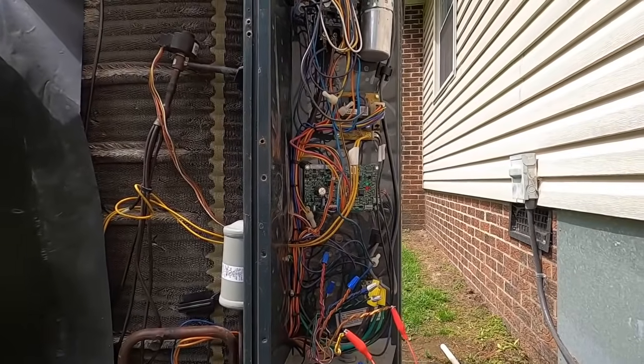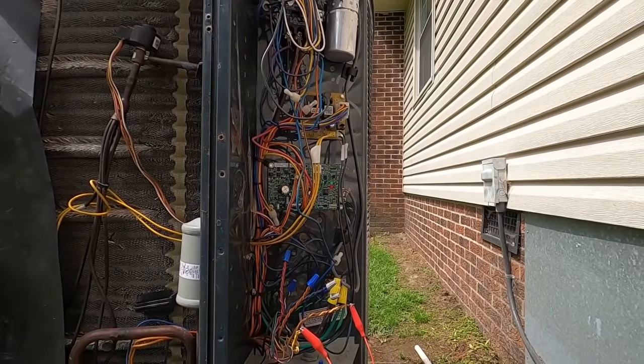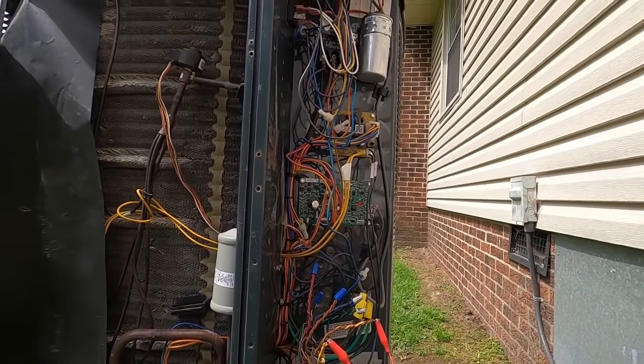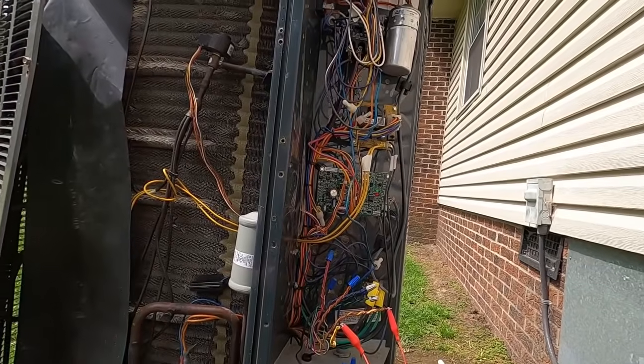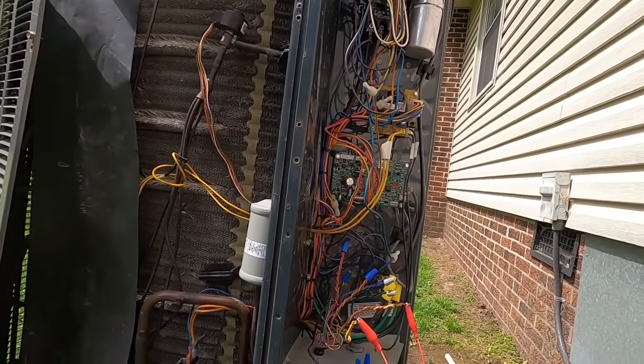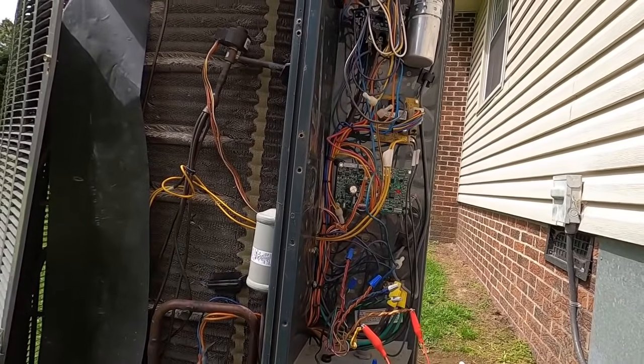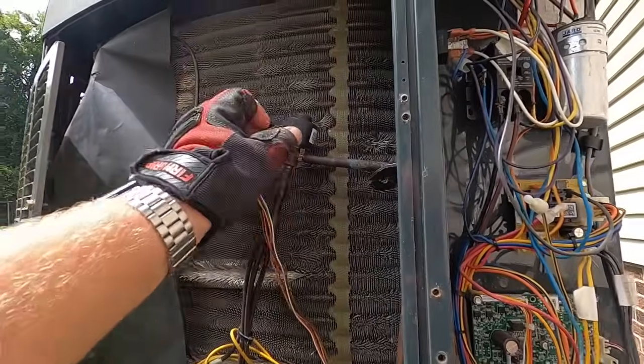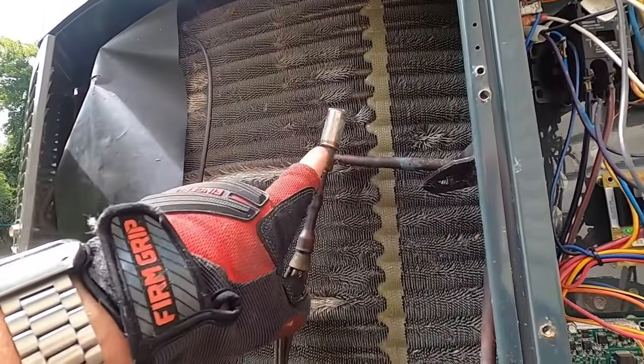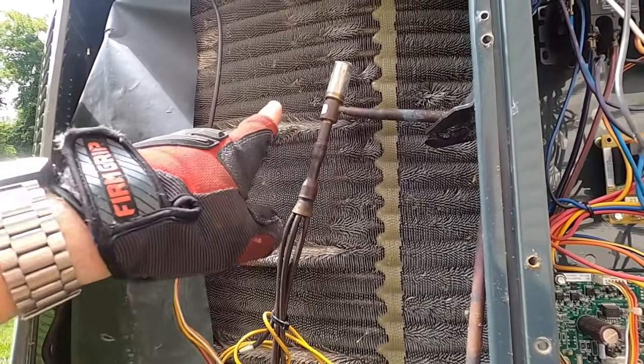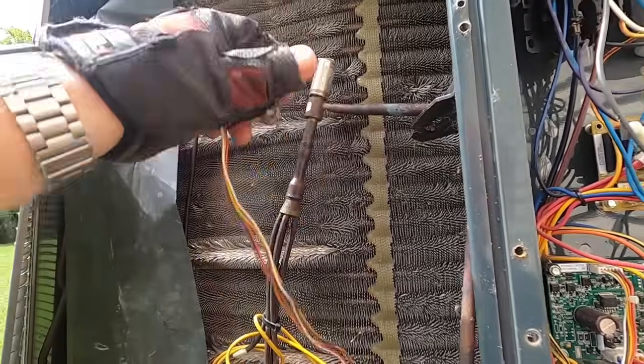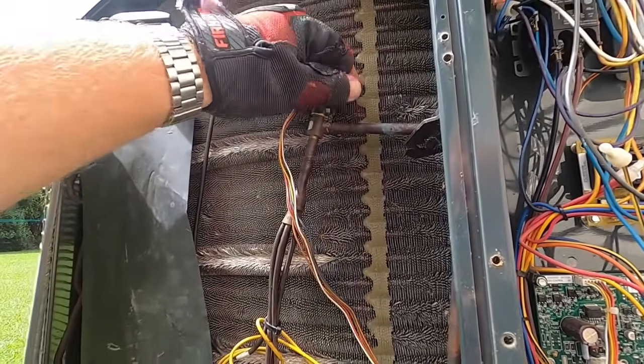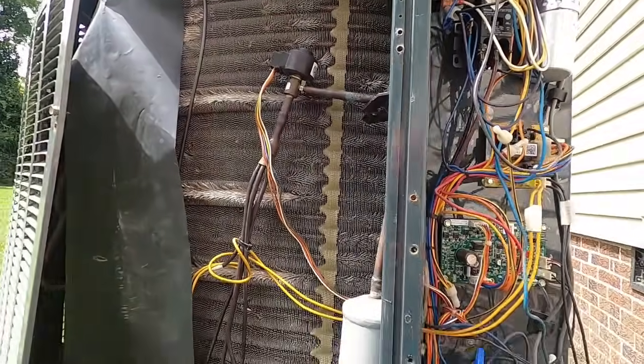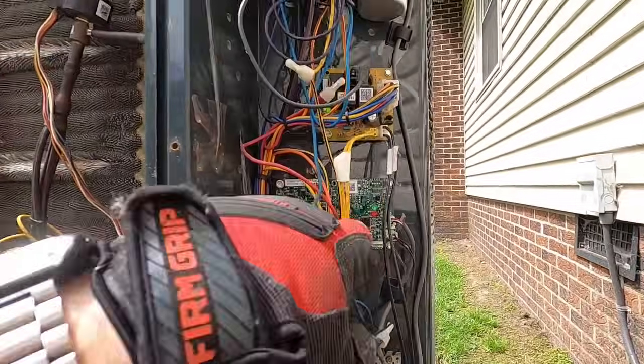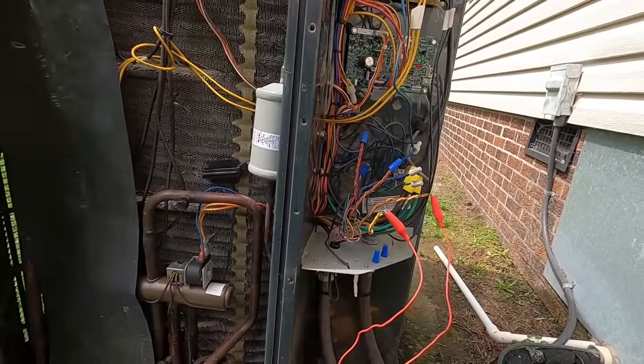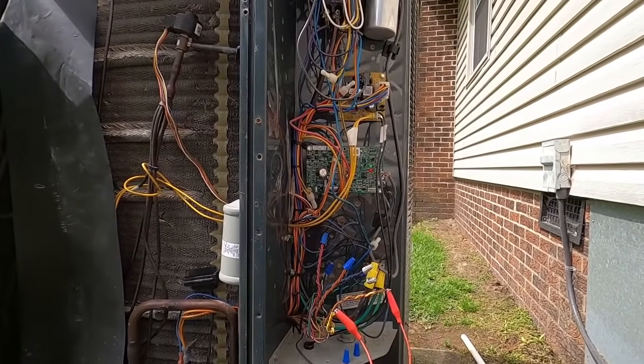These things are finicky, and you go out to them and they're showing this, that, and the other, and then you just turn off all the power and turn it back on, and it runs like a dream. But the only thing I can do is rule out the things I can rule out, which are the sensors and the stepper motor in there. We've never had a problem with the EEV, actual EEV on one of these things, which is this. Never had a problem with one of those getting plugged up or a leak once in a while at one of the braze joints, but we've never had a problem with that. It's either this or one of those two sensors. They're both checking good. So the one thing they all three have in common is being connected to the EEV board under the house in the air handler, and it may have a problem, so we're going to replace it.